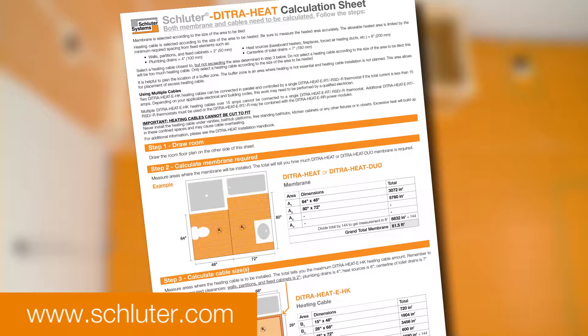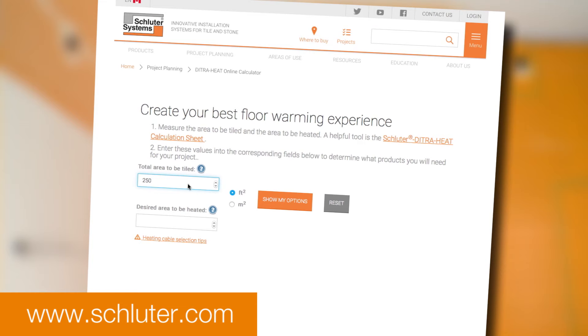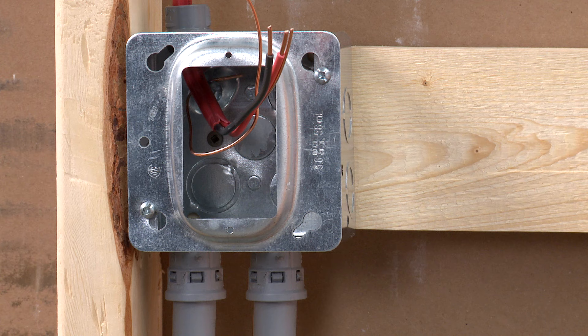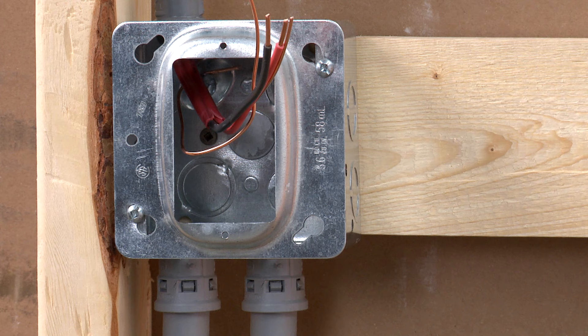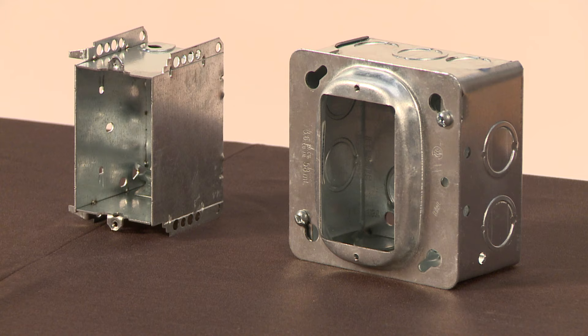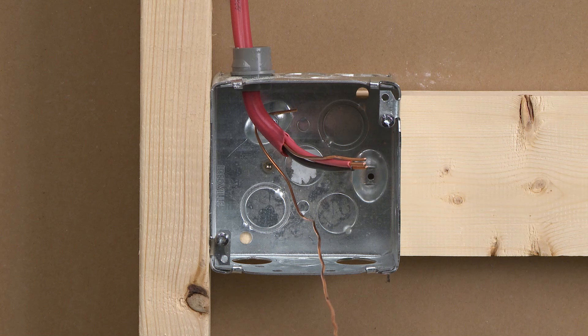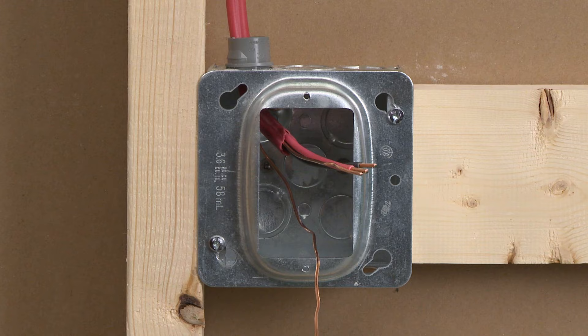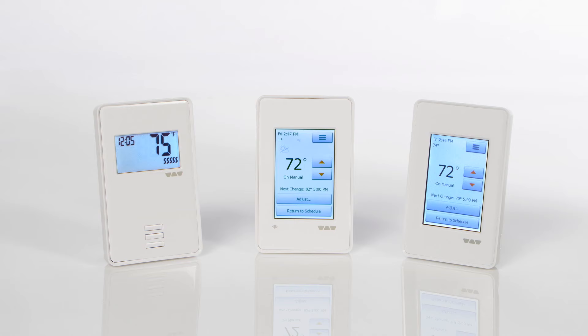Visit Schluter.com to use the DITRA-HEAT Calculation Sheet and online DITRA-HEAT calculator to help with your project layout. The electrical preparation has already been completed. A dedicated circuit has been run to the thermostat electrical box. A single-gang deep electrical box or a double-gang electrical box with a single-gang mud ring is recommended to provide room for the wiring. The junction box must be sized according to the electrical code effective in your region.